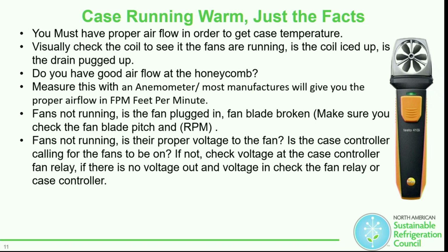Also, you have to remember it has to do with some of the programming. Some of these Hussmann cases require the fan relay to be on even during defrost. What switches that is what I call the fan-pan relay. It gets an electric signal from the defrost heaters and switches the power going to the fan over to the actual pan heater itself. Also, in some of the programming in these case controllers, the way the fans are brought back on might also interfere with how that pan heater is on.